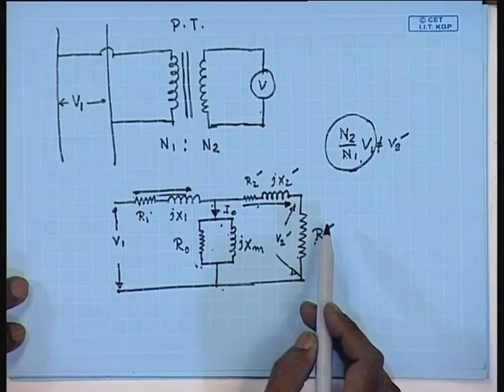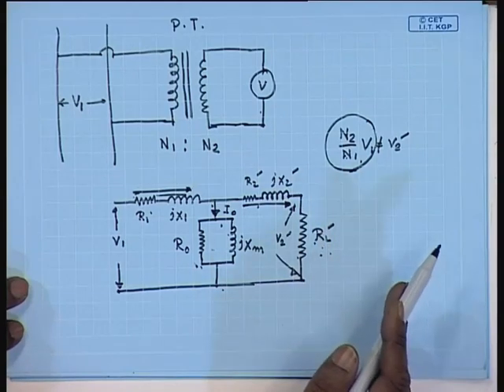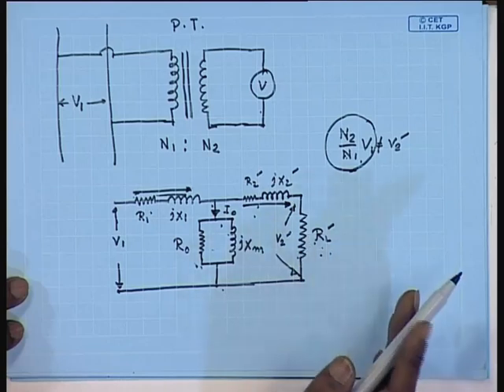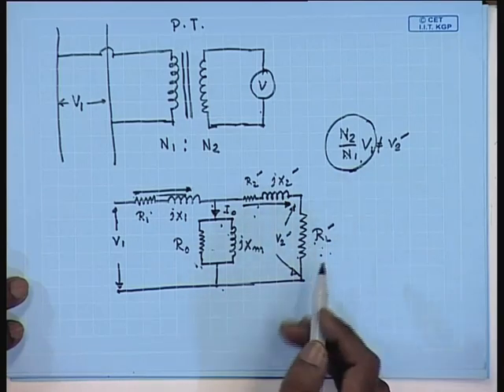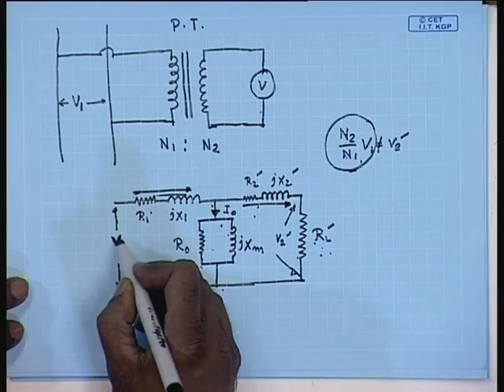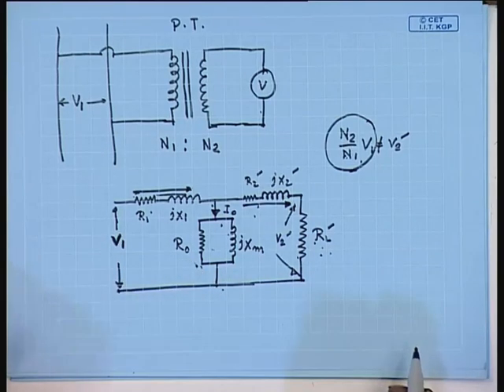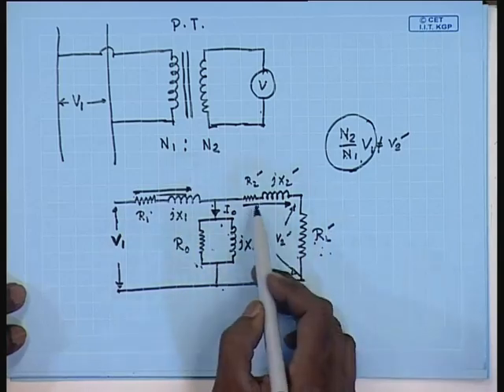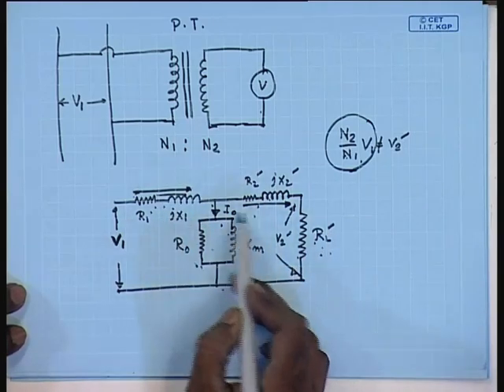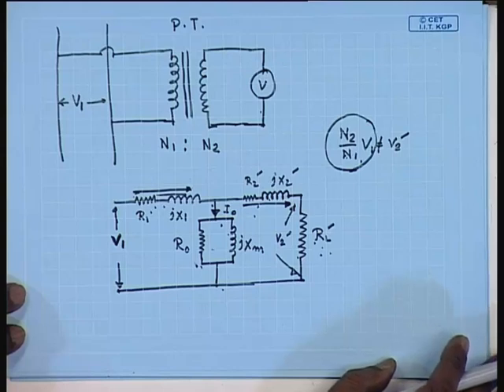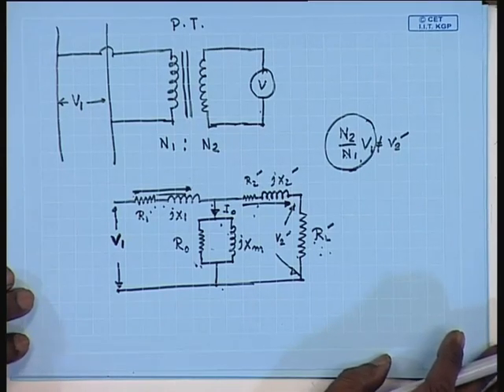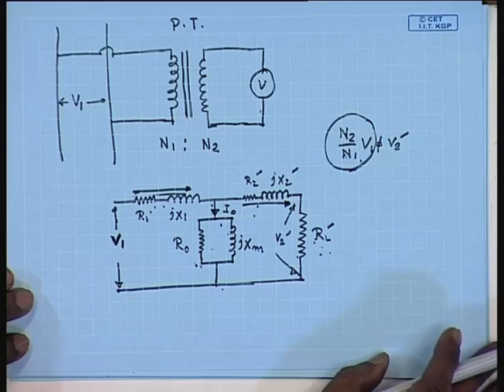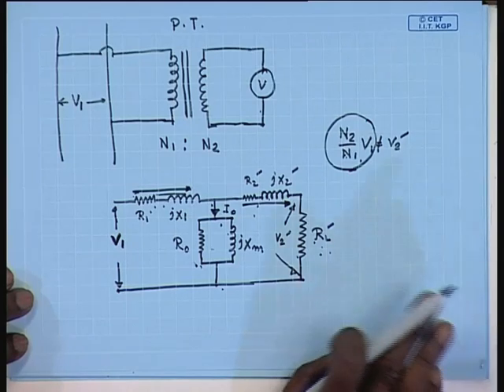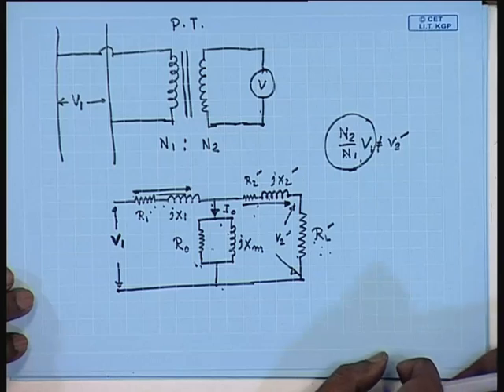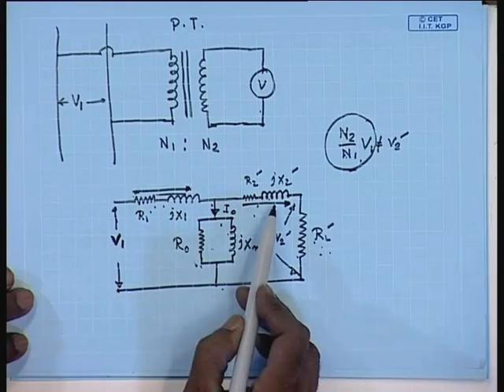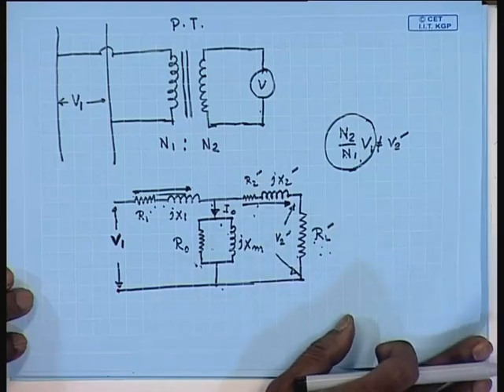So, it is necessary that a PT is used with a particular voltmeter, so that the current drawn by the meter does not change. Even then, it will change to some extent as V1 changes, but at least if we can reduce this, the regulation will be negligible. Hence, a PT series impedance will be very close to 0. It is imperative that the secondary of the PT should never even accidentally be short circuited, because then a very large current will flow, its impedance is almost 0 and will destroy the instrument.